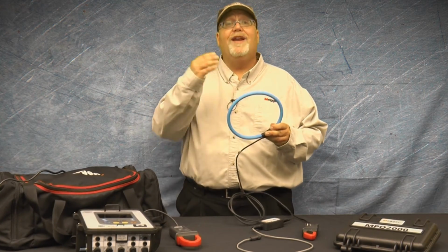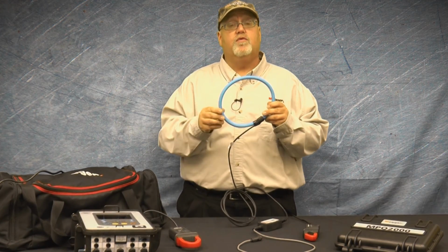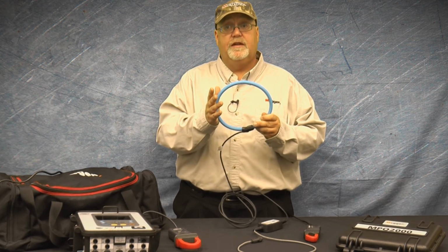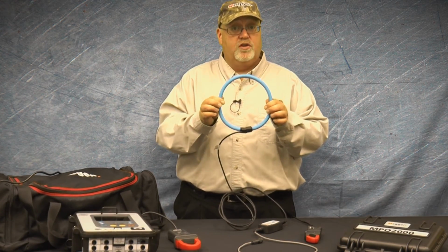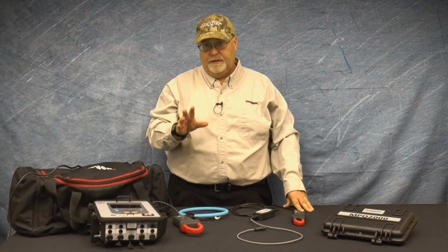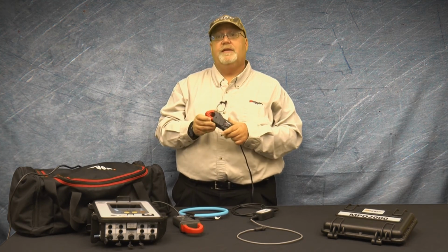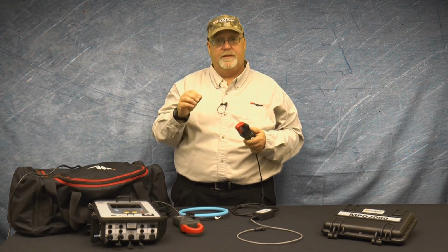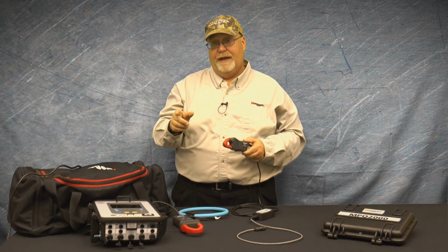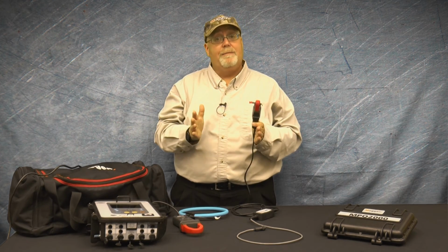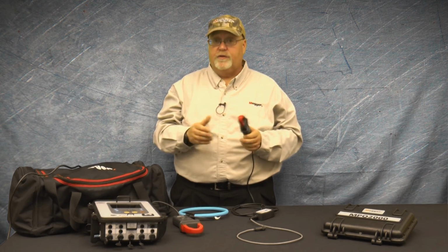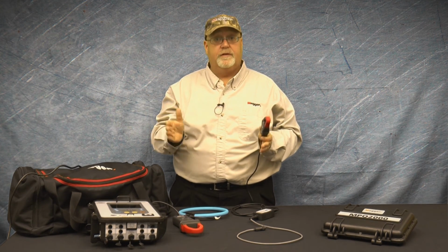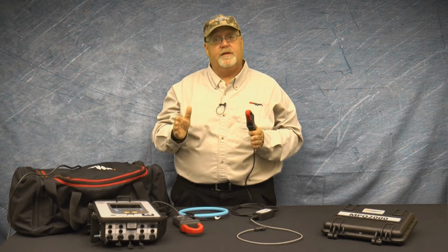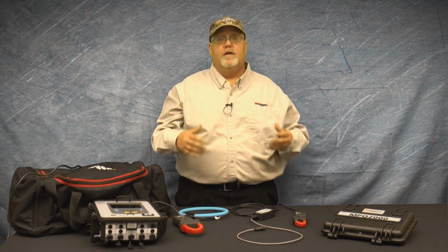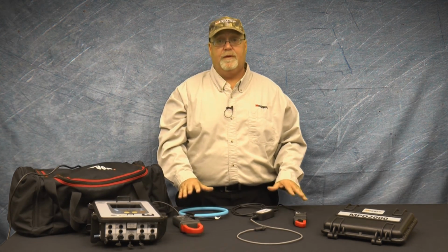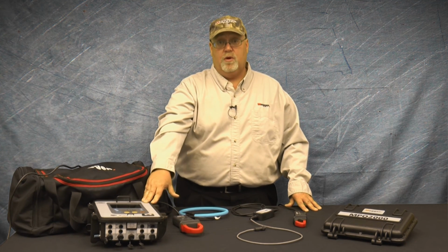Step 5. What is the voltage on the line you're going to be putting the CT around? You want to make sure that the CT is rated for that voltage level and the insulation provides proper protection. Another thing to keep in mind is if you're taking a measurement in a substation on the secondary of a substation CT, take note of the bandwidth of that substation CT. Typically, these have limited bandwidths, which means they can cause inaccuracies if you're attempting to do a harmonic analysis. So this is something to keep in mind if you want to do harmonic studies in substation environments. So remember, selecting the proper current clamp can be critical to performing a good power quality analysis.